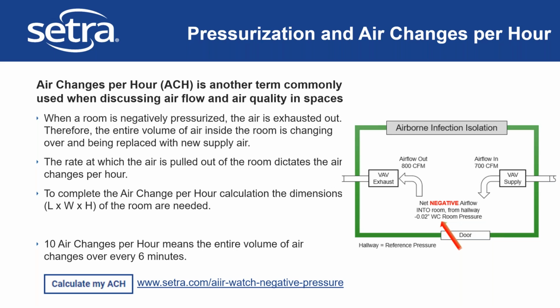So length, width, and height of the room tell you the volume of air that's in there. You can just use the actual wall dimensions. You don't have to worry about things like furniture and stuff, getting to that level of detail. Using the general dimensions of the room and the airflow of the room exhaust, the total airflow, that will allow you to calculate the total air changes per hour that you're generating in this space.